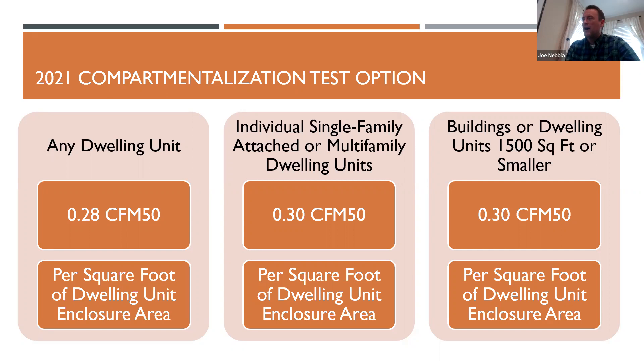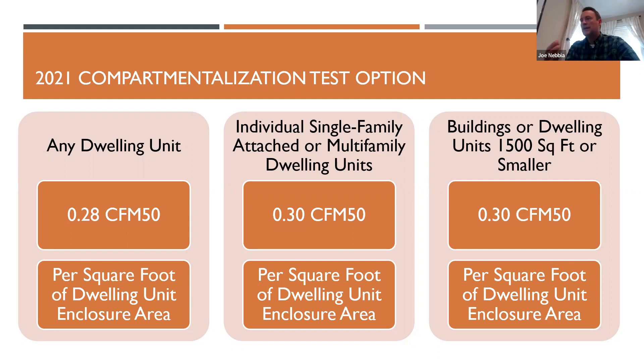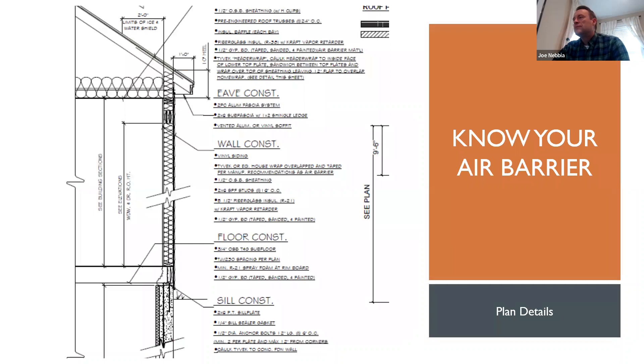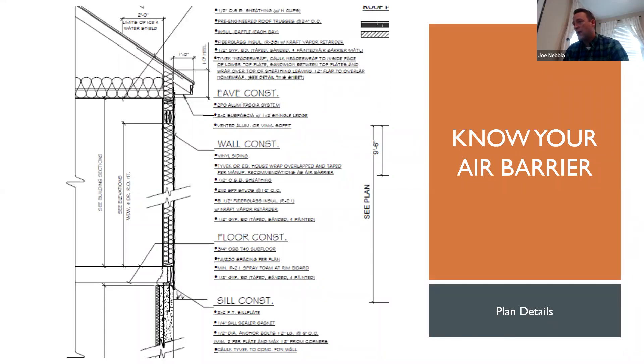This is just another option. If you don't want to do the 3 ACH or 5 ACH-50 test, you can do 0.28 CFM-50 for any dwelling, or 0.3 for attached dwellings, multifamily, and small units. Something to know whether you're doing CFM-50 or ACH-50 is you need to know your air barrier if you're going to pass regardless of the target. If you can't show where your air barrier is on the building plans, you don't know where it is, and you're not going to pass your blower door test except possibly by luck.